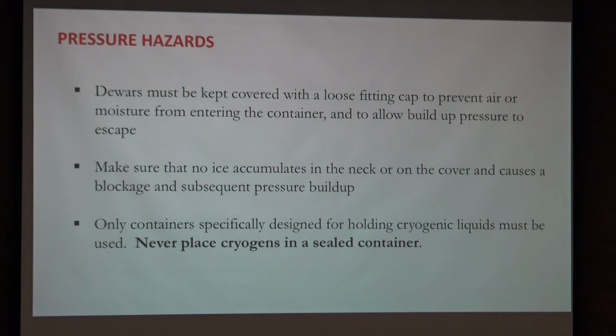And once your dewar has high pressure, it will essentially turn into a bomb and present a hazard in its own right. We have had this in our department. So if you have these open dewars, you want to keep them capped off with a loose-fitting styrofoam cap that will protect you from splashing cryogen, but will also not allow any pressure buildup, as it will come off easily if the pressure inside builds up too much.